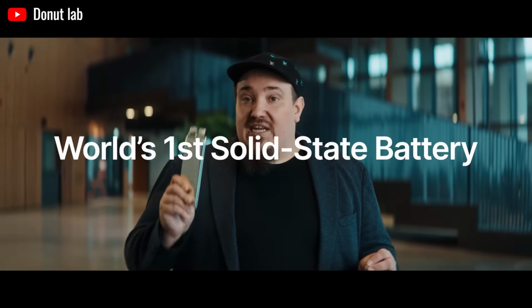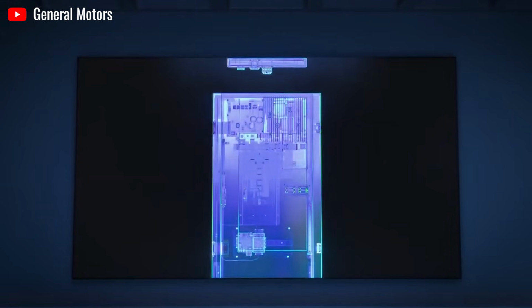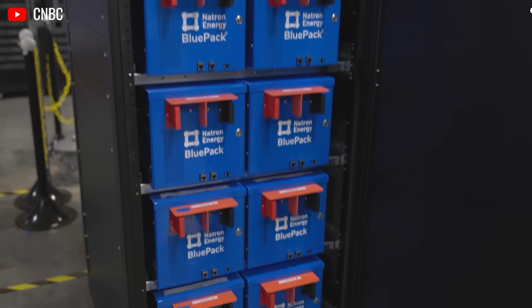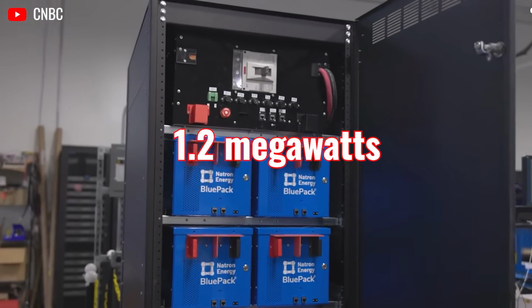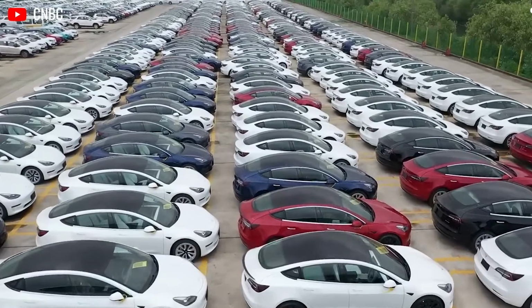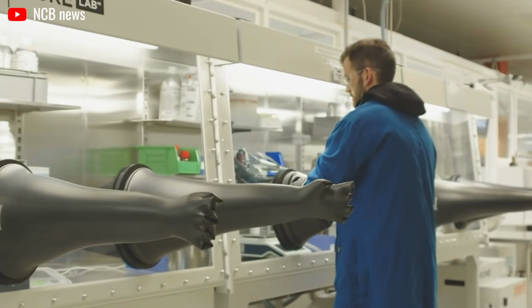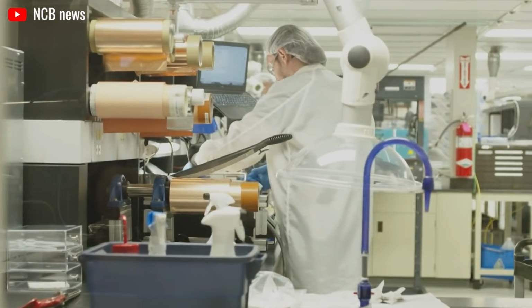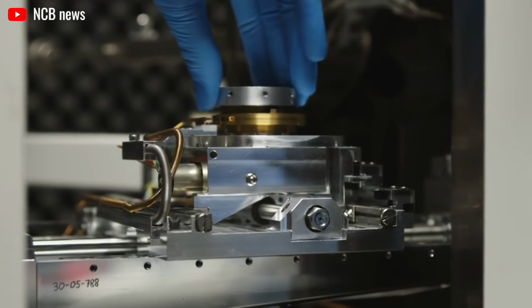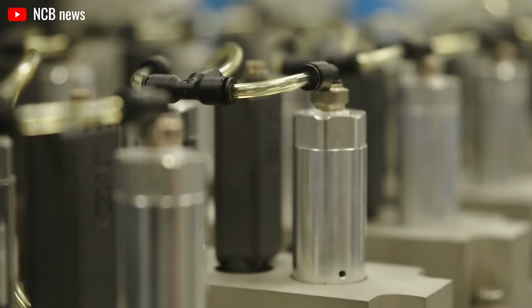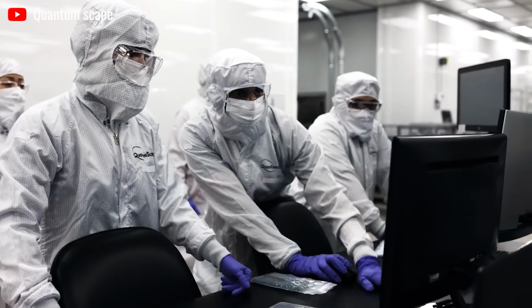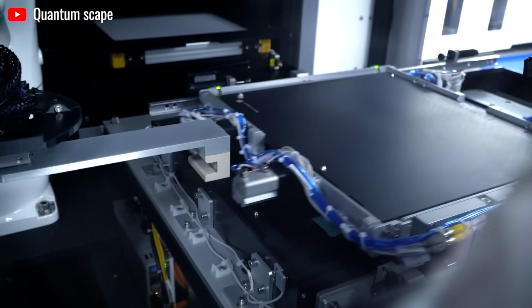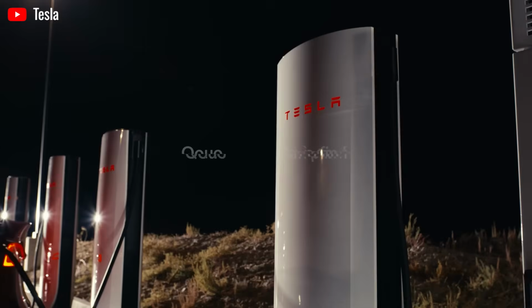Now, apply Donut Lab's 5-minute claim to a realistic vehicle. A 100 kilowatt-hour battery charged in 5 minutes requires a sustained power delivery of approximately 1.2 megawatts. This is not a rounding error. In fact, 1.2 megawatts equals 1,200 kilowatts. Moreover, it is nearly 5 times higher than Tesla's fastest chargers and roughly equivalent to the peak load of a small industrial facility. Even more critically, many highway substations are not designed to deliver that level of power to a single outlet. This is where expectations quietly break.